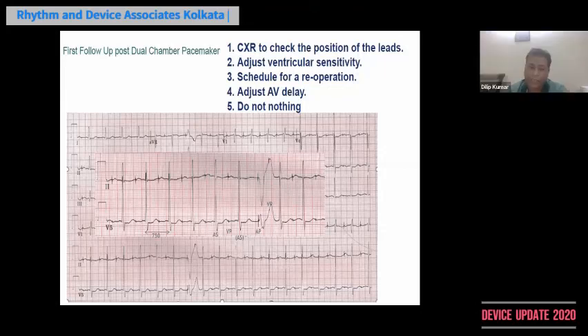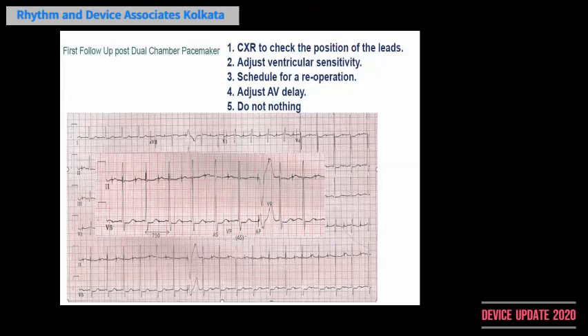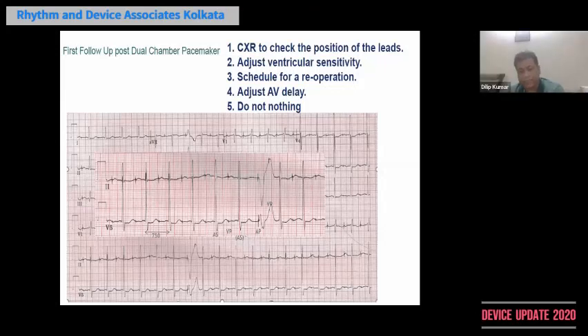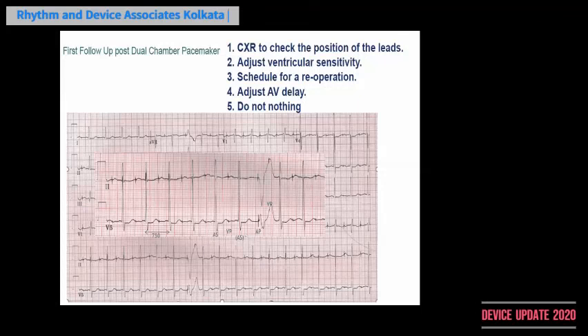Literature says the important thing, Dilip, is that the 2 spikes in the QRS will be separated by at least the AV delay. That much AV delay is going to be there, because you can have such a pattern even with a dislodged atrial lead. But in that case, the spike will come at the ventricular escape interval. Here, if you just change the lead, the first spike will instigate a QRS, but within the AV delay time you will have another spike in the QRS itself. So that AV delay will be maintained.